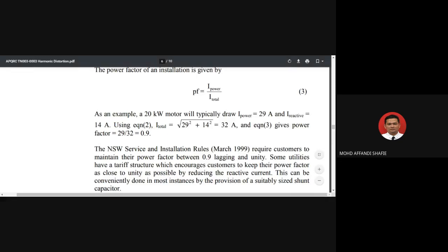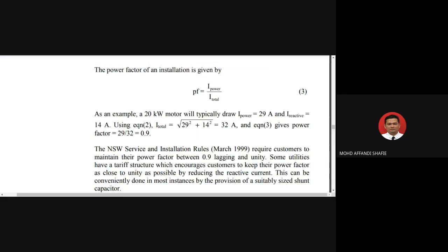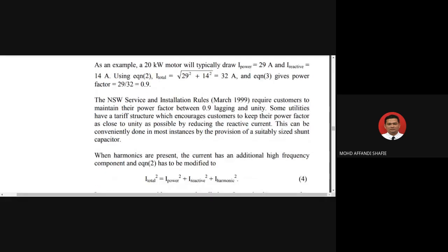As an example, a 20 kilowatt motor will typically draw I power equal to 29 ampere, and I reactive current is 14 ampere. Using equation 2, we can get I total equal to 32 ampere, and equation 3 gives a power factor of 0.9. So the NSW Service and Installation Rules of March 1999 required customers to maintain their power factor between 0.9 lagging and unity, but in Malaysia it is 0.885.